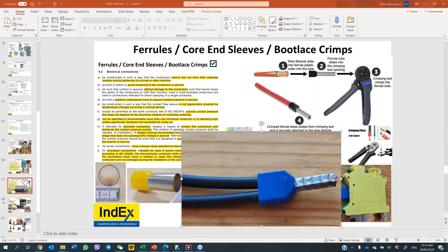What is the meaning of termination? What is the main reason for termination? The meaning of termination is the connecting of these two cores or two bus bars. A termination is where you're terminating, connecting something together. What is the main reason for termination? Because we can't always run one cable the entire length. We can't just have a fly lead, but you're always going to have a termination anyways. It's to get a good connection, to reduce the resistance, to reduce the heat, to not have any voltage loss, you know, I2R losses due to heat, yeah. Not have any increase in current.